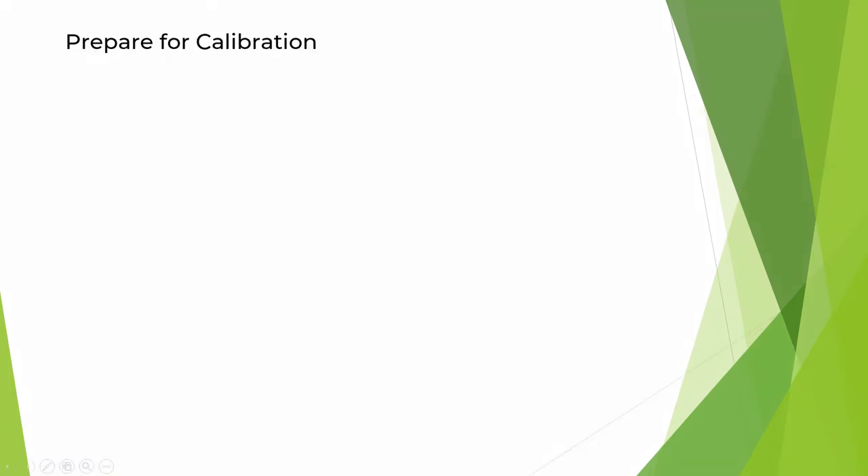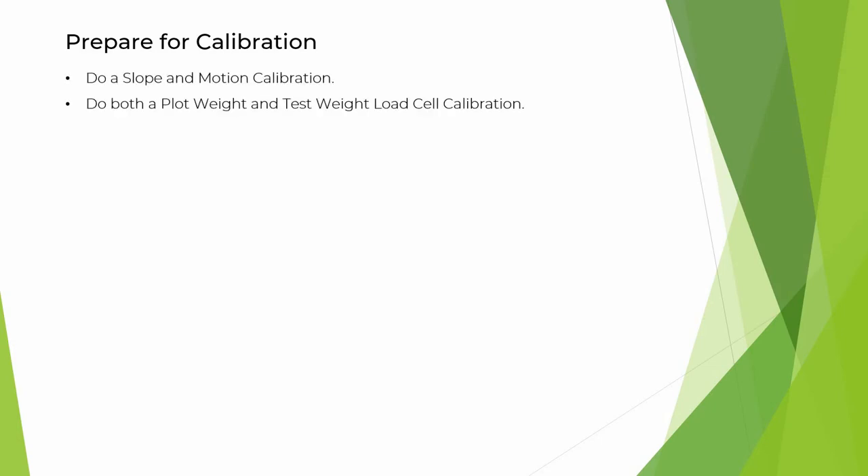Here are some things to do to prepare for your M2.0 calibration. Do a slope and motion calibration, and do both a plot weight and test weight load cell calibration.